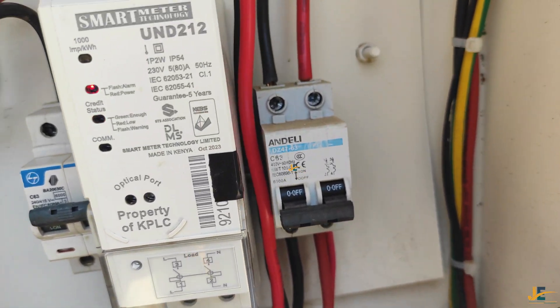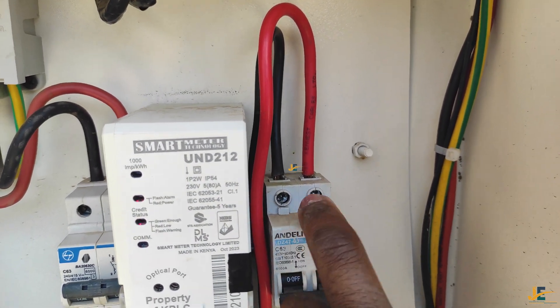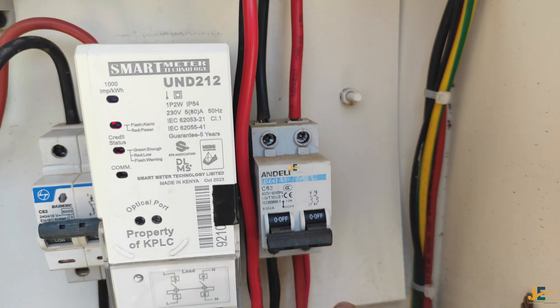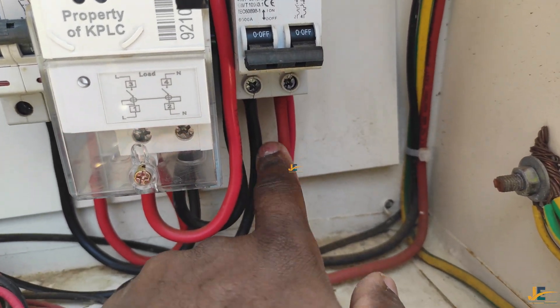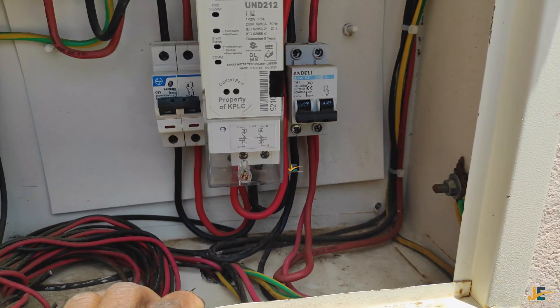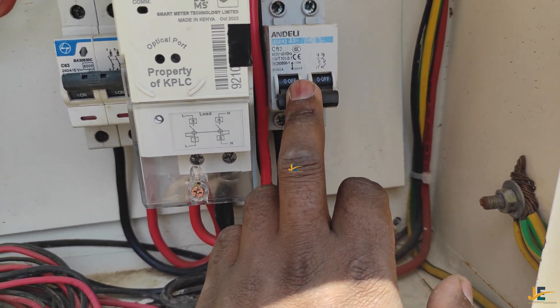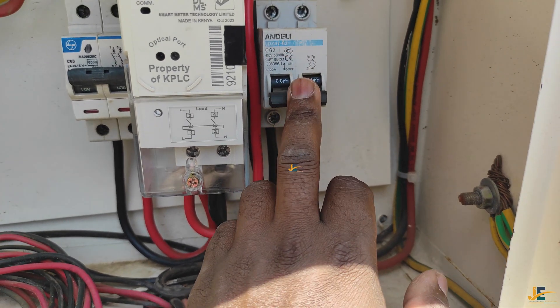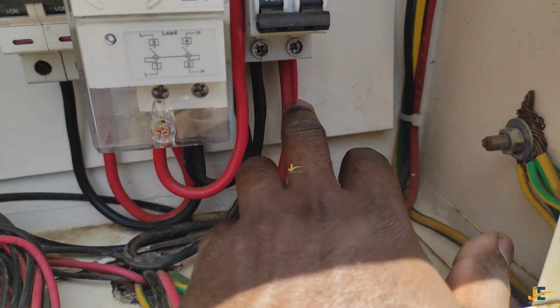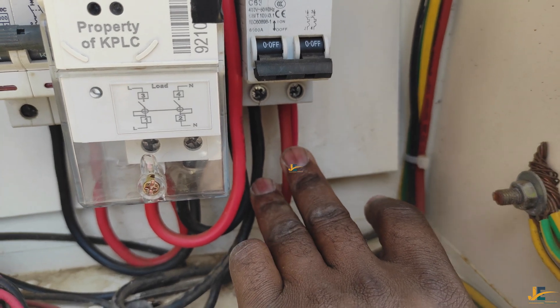These two output wires from the meter come into this second MCB double pole as its input. Once we have power here, we can get our load from the lower side of this double pole. The advantage of using this extra double pole is that in the future, if you'd like to add another detached load or detached house load, you don't have to open the terminal cover — you just come to this second double pole and add that extra load.